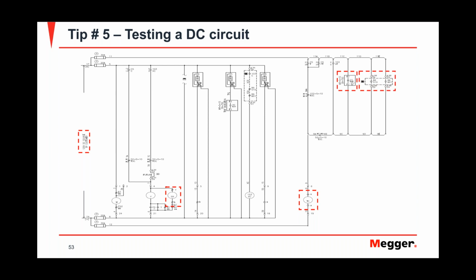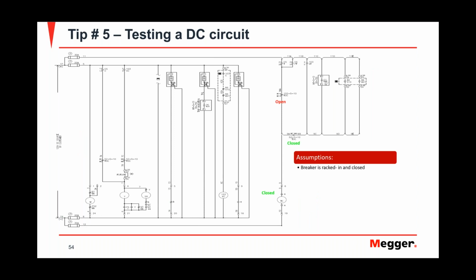That's another way. Lastly, and I'm going to go really quick through this, it's going through testing DC circuits. Let's say you have a 125 source that's controlling your breaker in this case, and you have your close coil and your trip coil, you have an 86 device here tripping, and you have your relay contact, right? The first time I was out troubleshooting, I wasn't very good at understanding what voltages I should see on my multimeter. So I'm going to give you a couple of examples. I'm going to ask you questions to see what your understanding of DC circuits is.